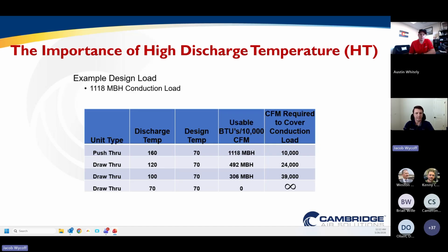Because when you're using 100% outside air equipment, in this example, if it's 0 degrees outside and the design temperature is 70 degrees inside, heating that outside air up from 0 to 70 degrees only provides BTUs that are usable to cover your air load.